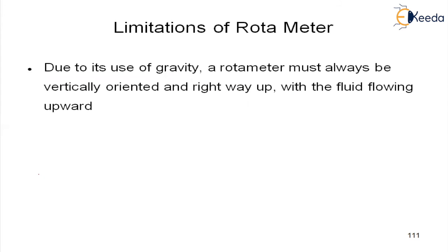Limitations. The disadvantage, the drawback, is that because of the use of gravity, the rotameter must always be vertically oriented, right way up, with the fluid flowing upward.